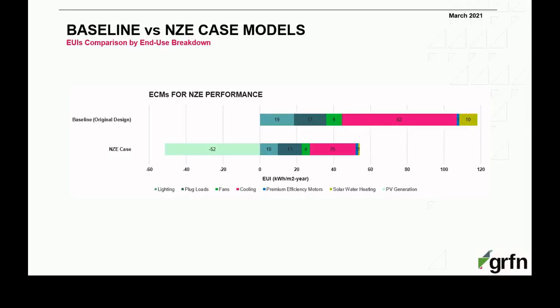Now, if you look at the other systems, we also have a good amount of reduction. We have used premium efficiency motors, electronically commutated motors, solar water heating, and better equipment in terms of plug loads and lighting. Also, we have much more efficient lighting. So all these things have contributed to the net zero, not only the reduction in cooling, but all other systems together. And by using almost all available space for PV, we got to the net zero energy building.